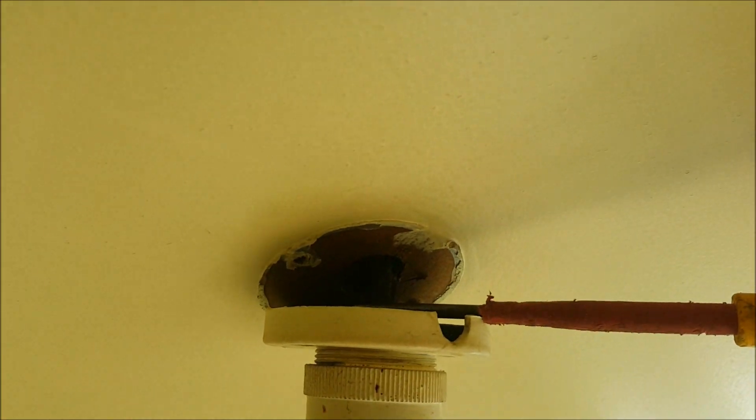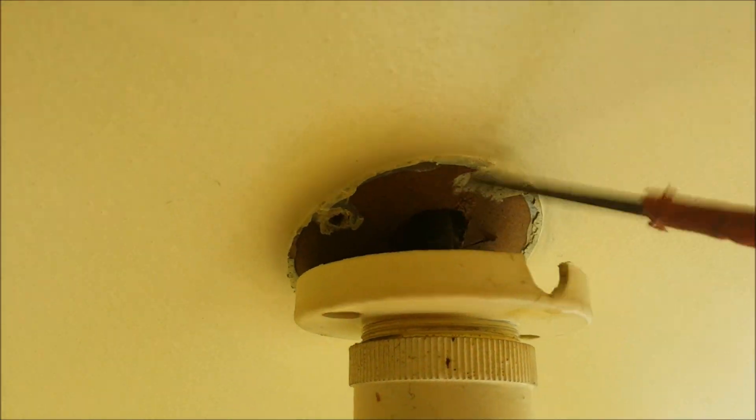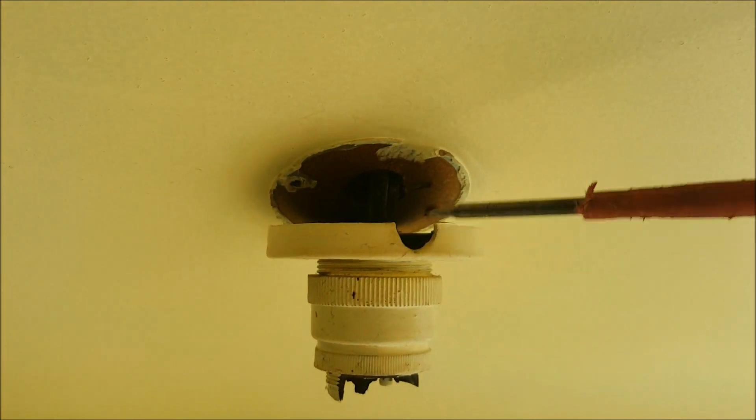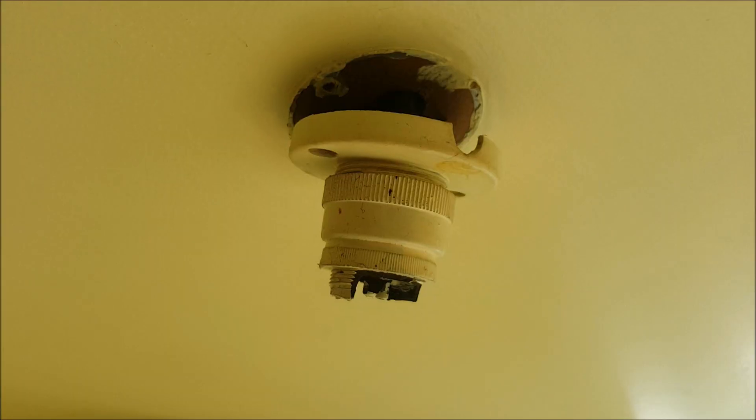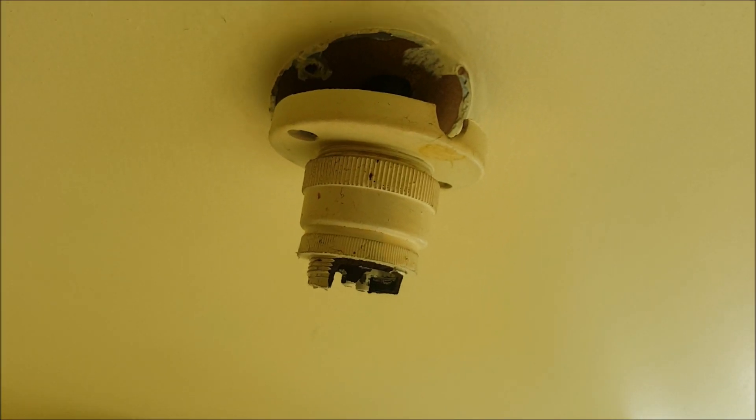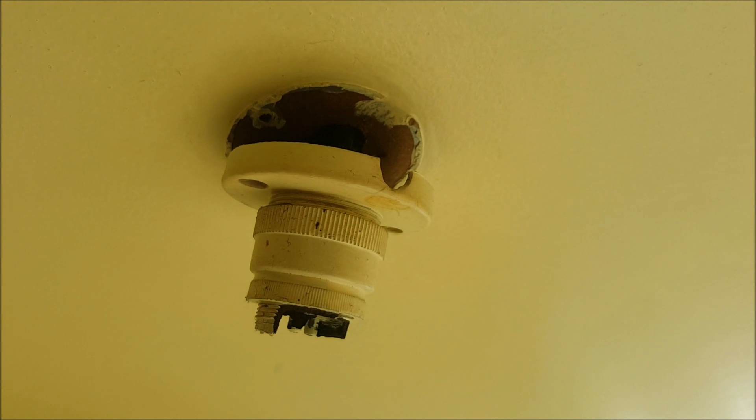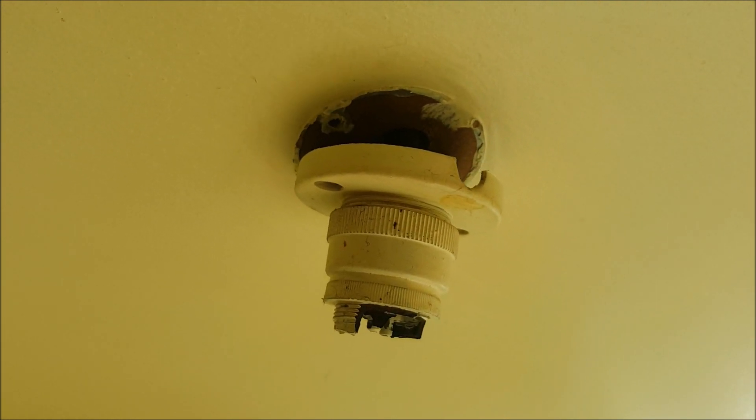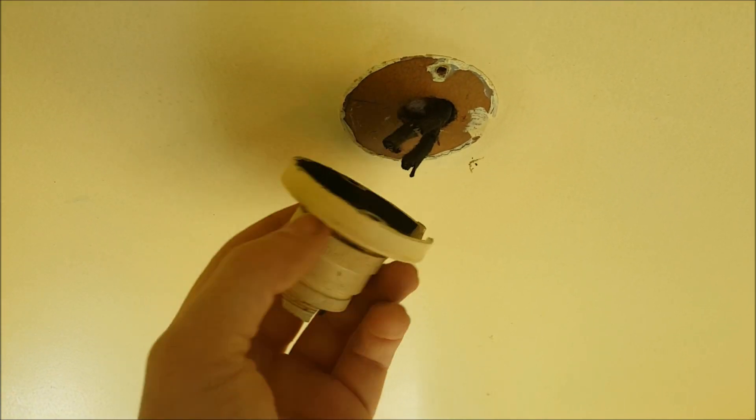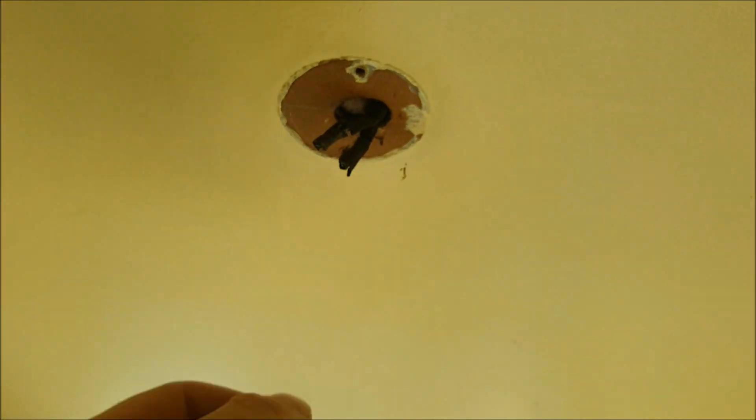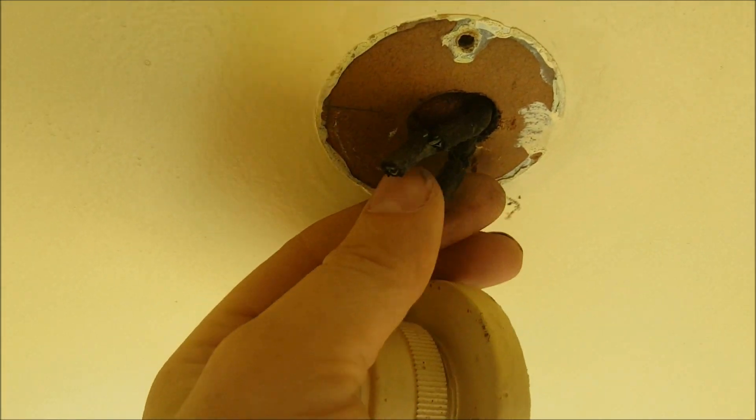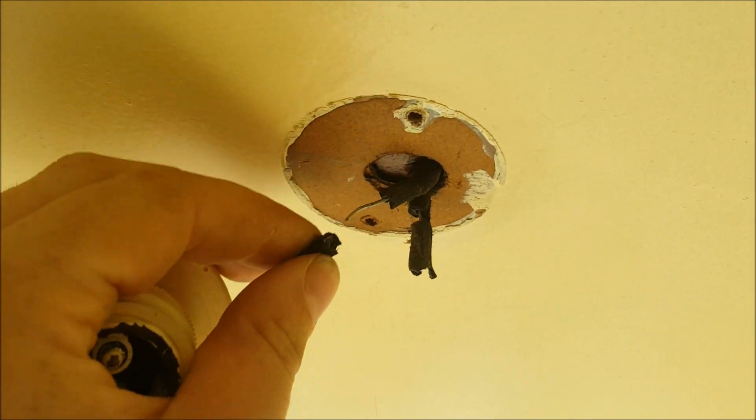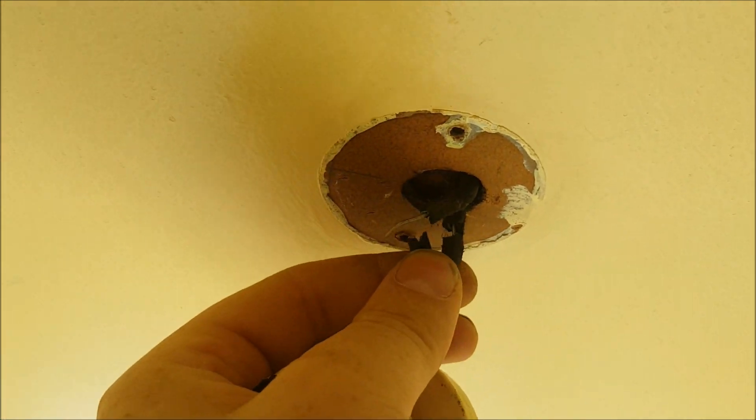So that black looking cable there, that's rubber. I don't know if you can see properly, but we're trying to rewire these days. If it's sitting there and it's not touched, it's fine, but the more you terminate it and the more you strip bits off it, the rubber just tends to fall off. So I just cut this off for ease. As you can see here, that's what happens to rubber - the insulation just falls off everywhere.